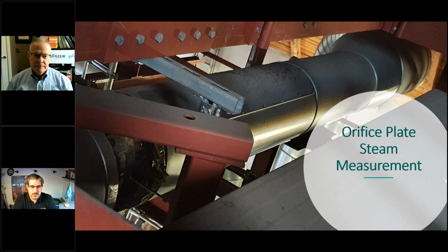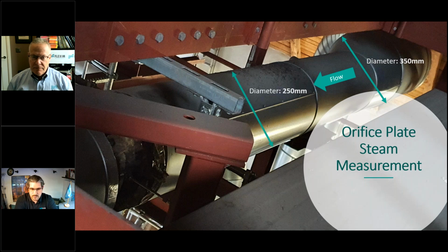So here's one example. Just recently, I made these pictures actually yesterday, where I was on site with our service. And this is a real steam measurement installed. You can see it on the right-hand side. The pipe comes up from bottom to top. So this is above a 20-ton steam boiler. So the flow direction goes from right to left. And the main pipe diameter is 350 millimeters. So the boiler output pipe diameter is 350 millimeters. But what you see now here is that you need a pipe diameter reduction down to about 250 millimeters. And here on the left-hand side is the orifice plate, the actual meter.